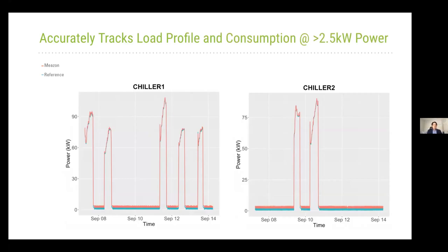So a different type of load that we found here was the chillers, and I'll describe why that difference occurred. We saw some different results in terms of the chillers. And what we have here is 1 week worth of data aggregated to 15-minute intervals for chiller 1 and chiller 2. As you can see here, this is a high power load. So we're talking about around 100 kilowatts. And what we see is that whenever the chiller is running, whenever we make this cutoff at 2.5 kilowatts, it highly tracks what our reference meters were collecting. However, whenever the chiller was idling, we saw some discrepancies. And we noted that when we discussed that with Meazon, and I think we can go to the next slide to explain that.